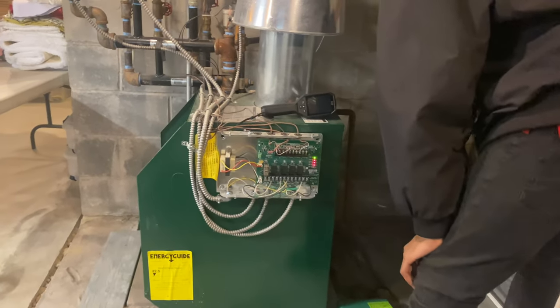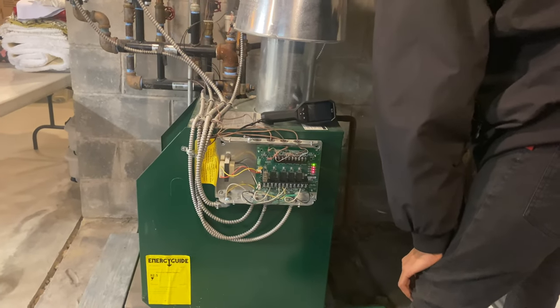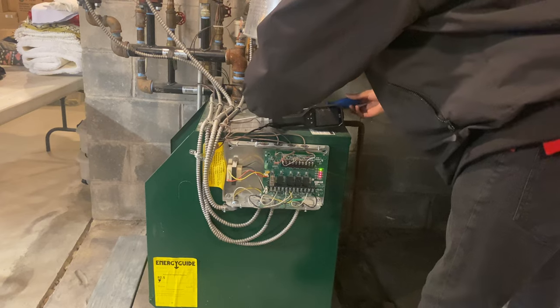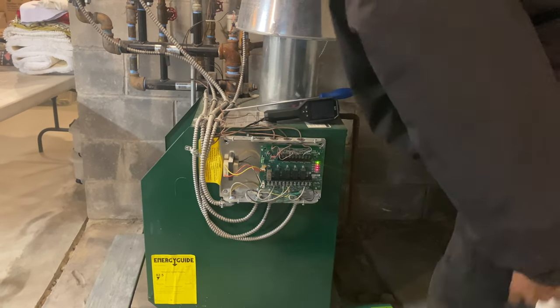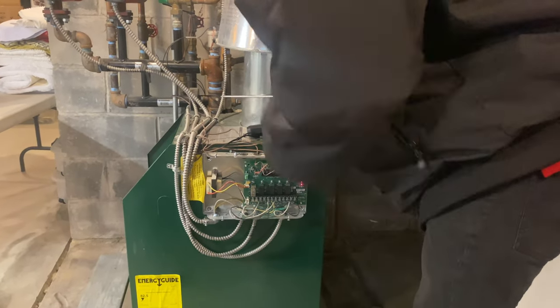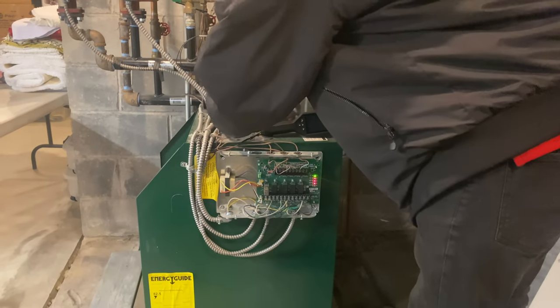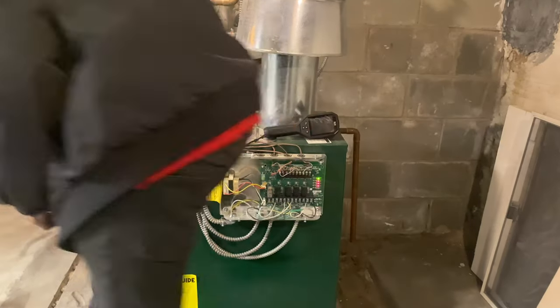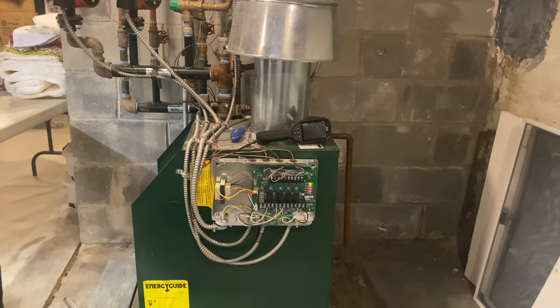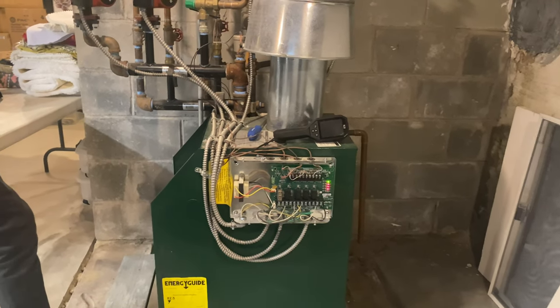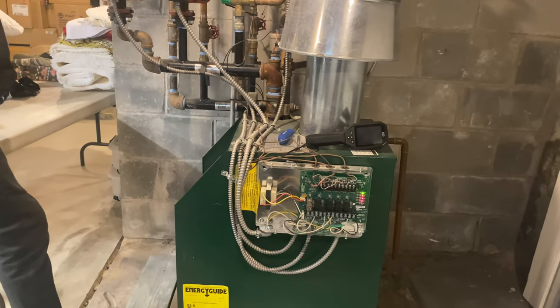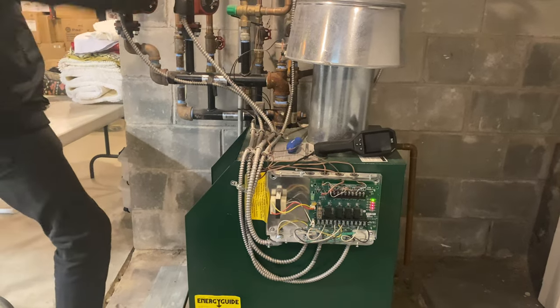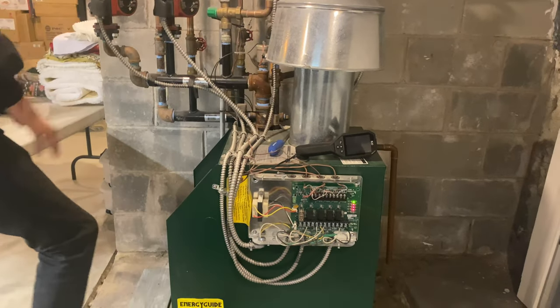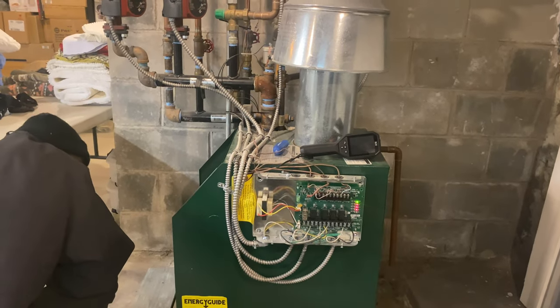So the problem we have right now is the boiler is turning off way too soon. I had you raise the thermostat up a little bit to see if the thermostat communicates with the boiler to turn on, and it does. So right now, zone one, which is first floor, zone two, which is the den and first floor bathroom, and zone three, which is the second floor, are all on right now. We're going to watch the boiler temperature and see if it turns off prematurely, and it should, because that's what it's been doing.